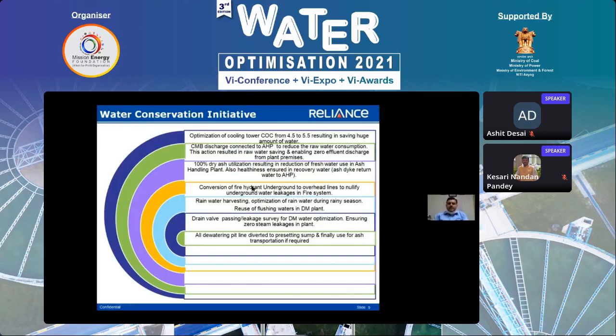For the last 3 to 4 years, we have achieved 100% ash utilization, and the majority of the ash is being transported in dry mode. That has reduced our water intake to the ash handling. Since our recovery system is also 100% available, all the water going to the dike, we are recovering 100% of that. So that has really conserved our water. We are not using fresh water; only the minimum amount is used in the ash handling.